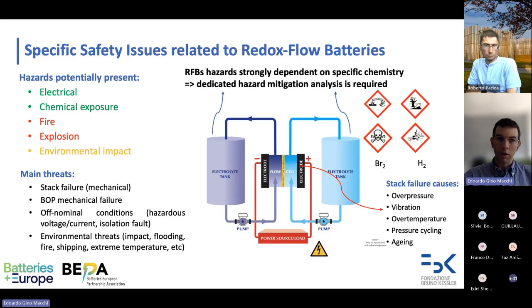Another point of attention is the environmental threats. These are of different types: impact, even during transportation, flooding due to extreme events, and external fire that can happen, of course. Fire in itself is not a risk for flow batteries, at least for most flow batteries. Of course, if we have hydrogen, that's a different matter, but for most flow batteries that are aqueous-based, with liquid electrolyte, that's not critical. But an external fire could create some threat, since we do have a fire load for the flow battery, although most of the battery is made of liquid.